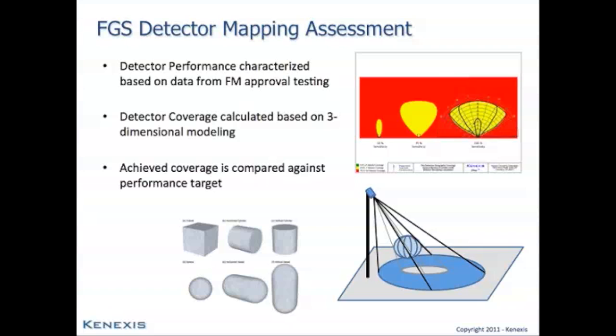And when performing a fire and gas detection map, the software tool or any tool or procedure that you use to perform modeling will need to faithfully reproduce the cone of vision of that specific equipment vendor, as different vendors will provide different cones of vision and have different performance characteristics. One can't simply use a generic model and apply it to all detectors. Different detectors have different attributes and different performance levels at different settings.